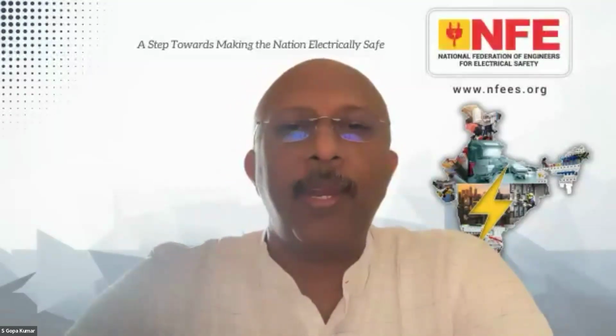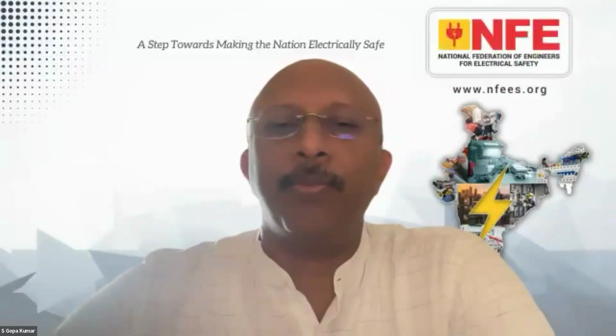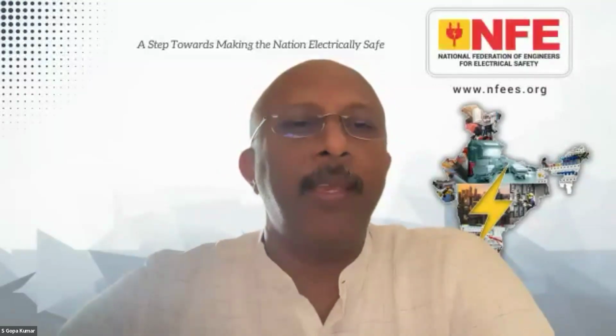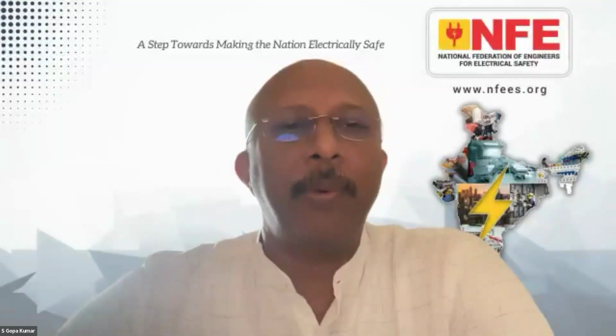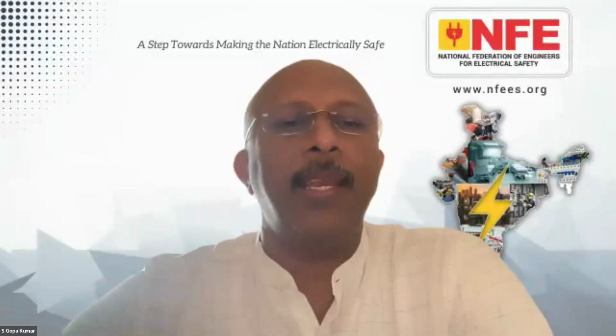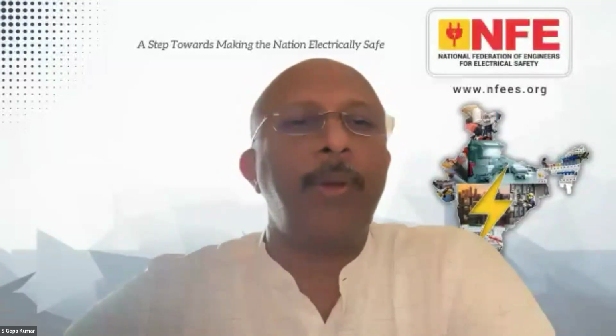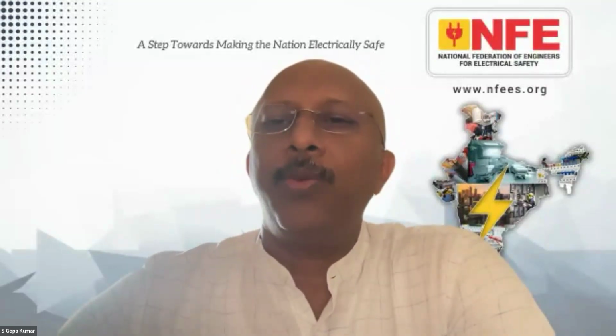Type B is the best option in such a case, but the problem is availability—most manufacturers in India don't supply Type B RCDs, and even when they do, it's at an exorbitant cost. Earlier, Tata supplied their portable chargers with Type B RCD, but later, in their newer vehicles, they changed it to Type A.